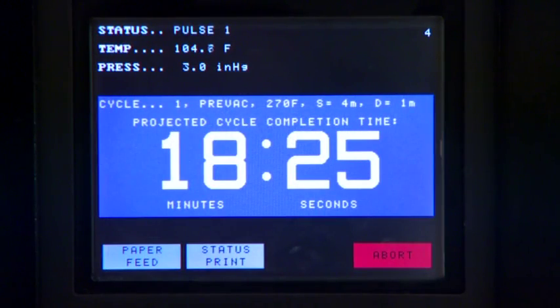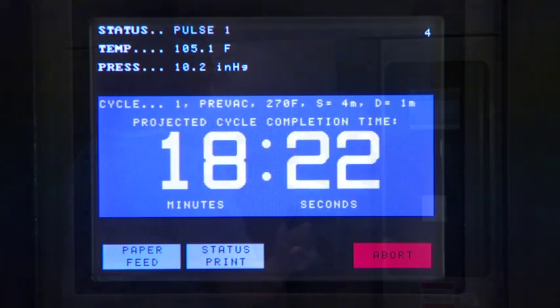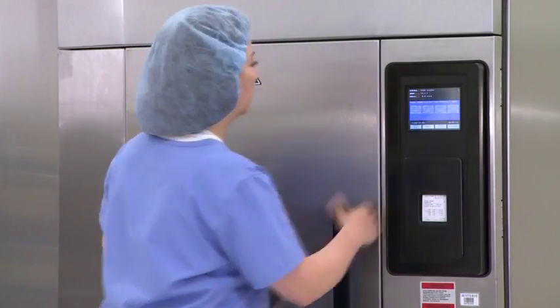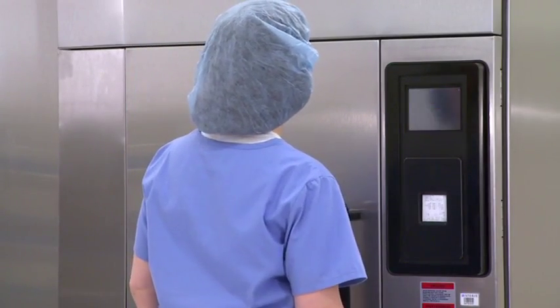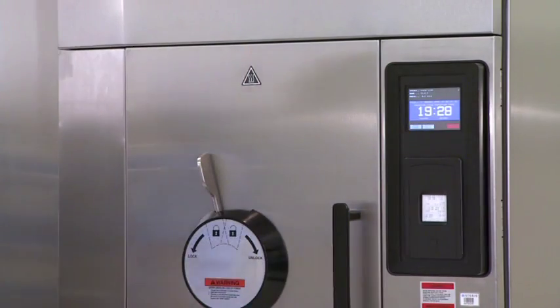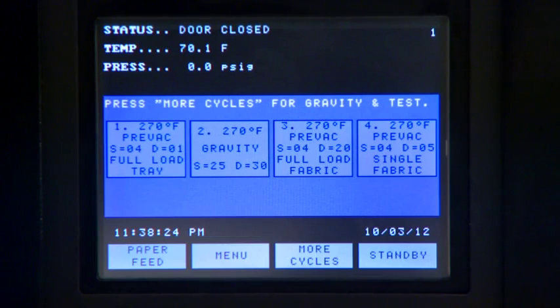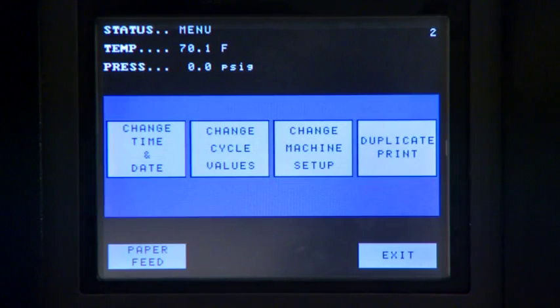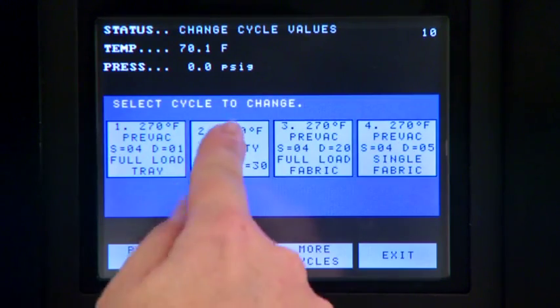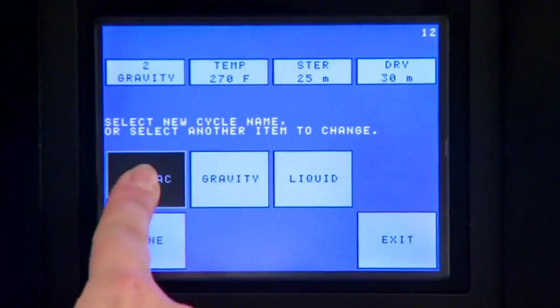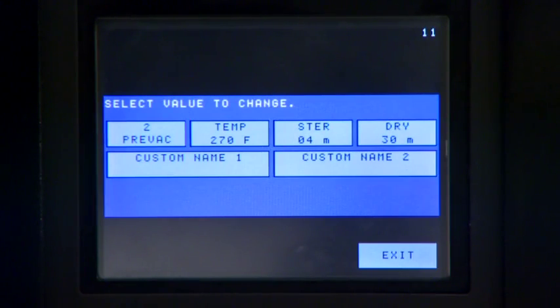If cycle parameters, sterilize time, dry time, temperature, other than the factory set values are required, it is the responsibility of the healthcare facility to consult and follow the device manufacturer's written instructions for processing. To adjust the sterilizer's operation, press the menu button. The Change Time and Date, Change Cycle Values, Change Machine Setup, and Duplicate Print buttons are displayed. To change cycle values, press the Change Cycle Values button. Then press the cycle button number you want to change. Choose the cycle type. Then choose the cycle parameter you want to change.